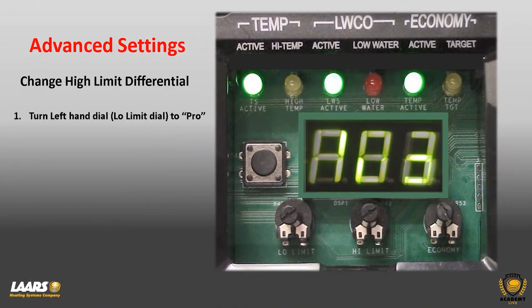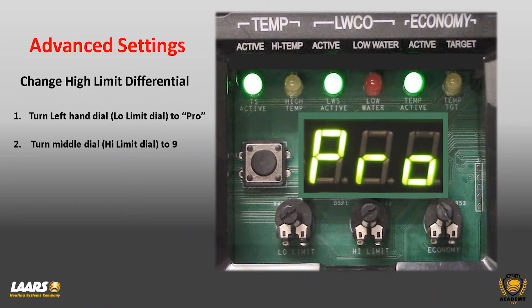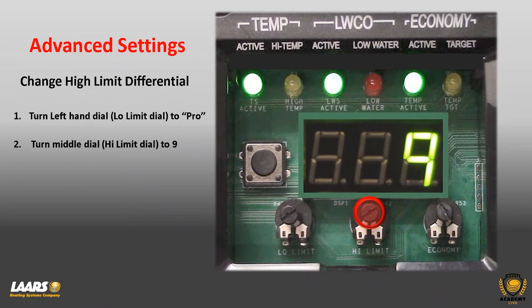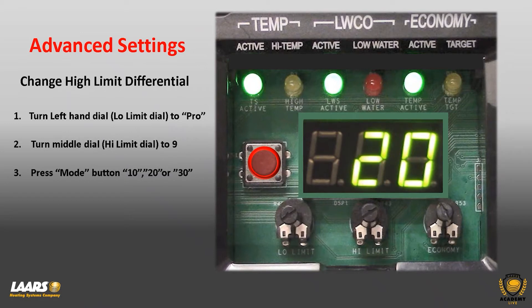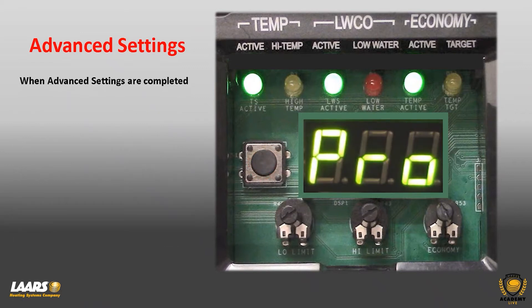To change the high limit differential — defaulted at 30 degrees — start in PRO for programming. Turn the middle dial until you see the number nine. Press the mode button once and it will show the defaulted setting of 30 degrees. Press it a second time and you'll see 10 degrees; press it again for 20 degrees. There are three options: 10, 20, or the default of 30. Scroll through until you find your value and be patient — it will revert back to PRO for programming.